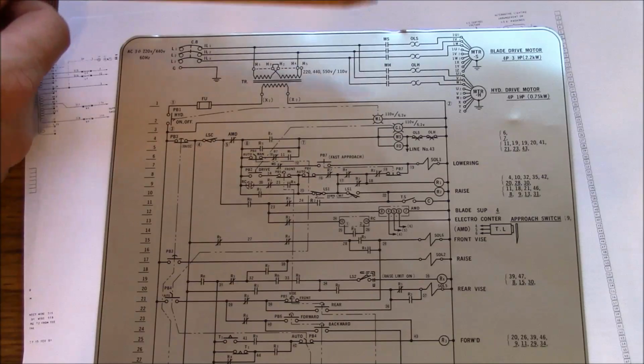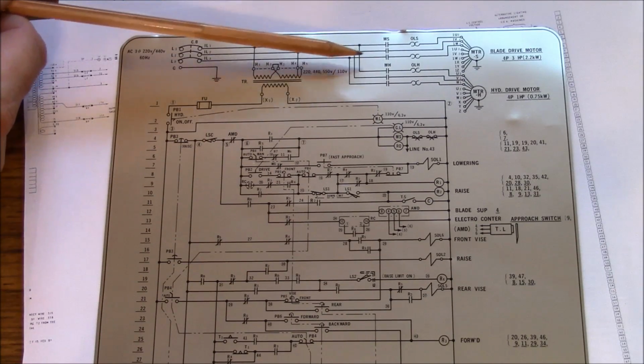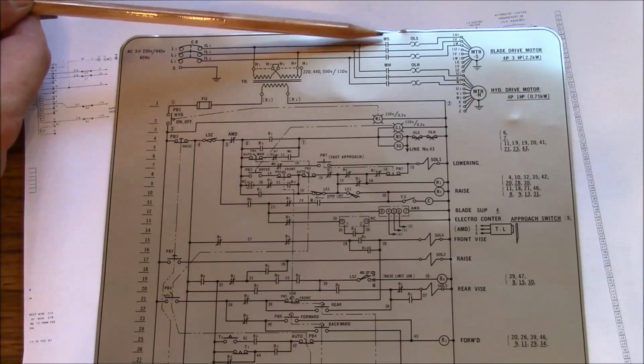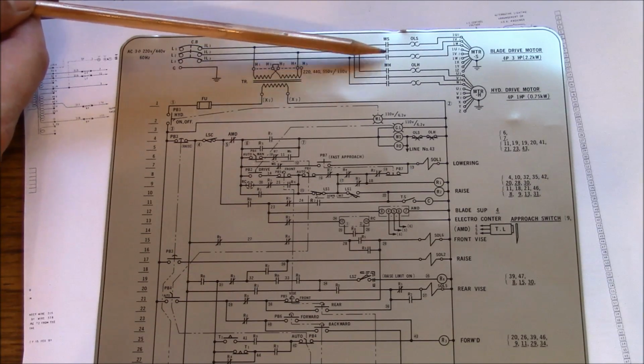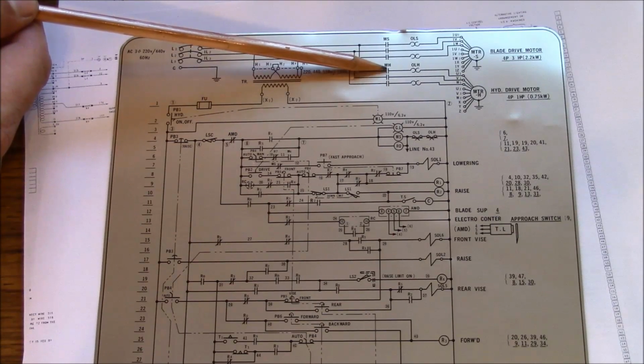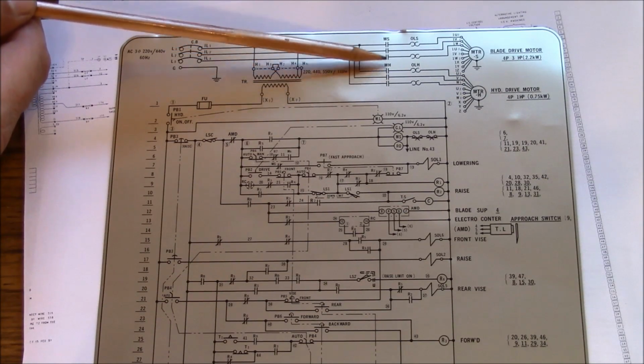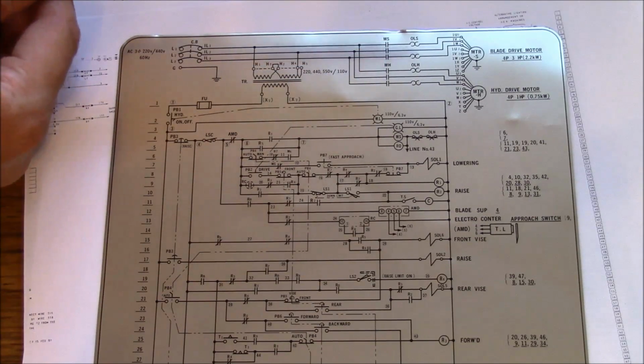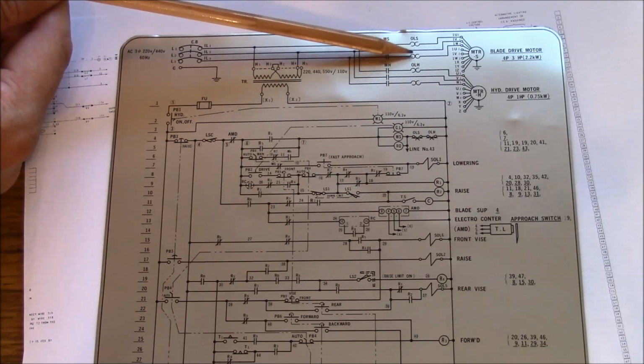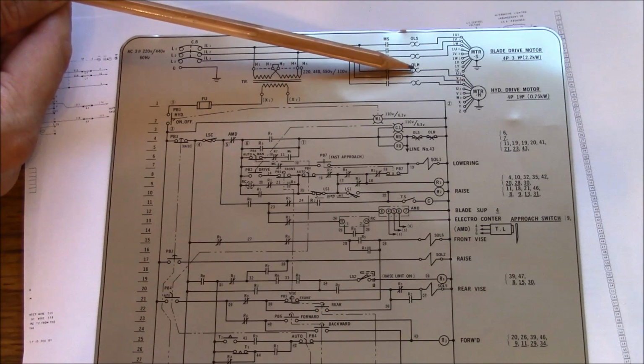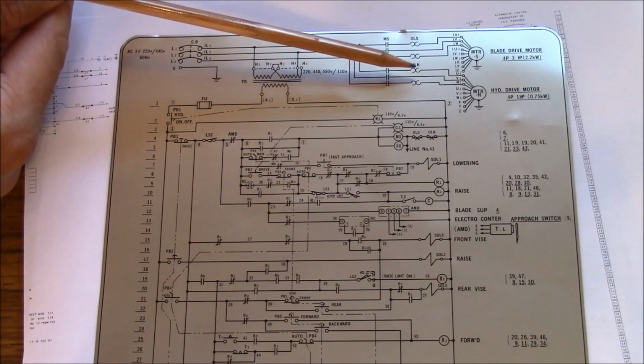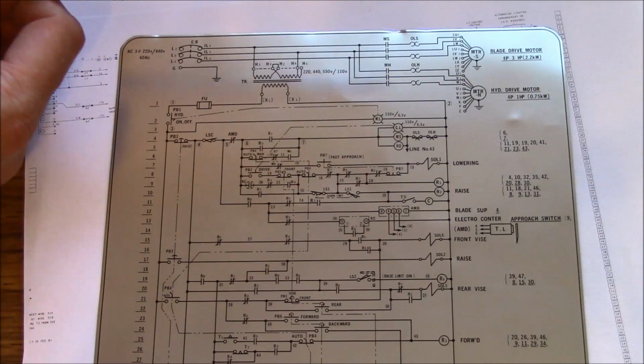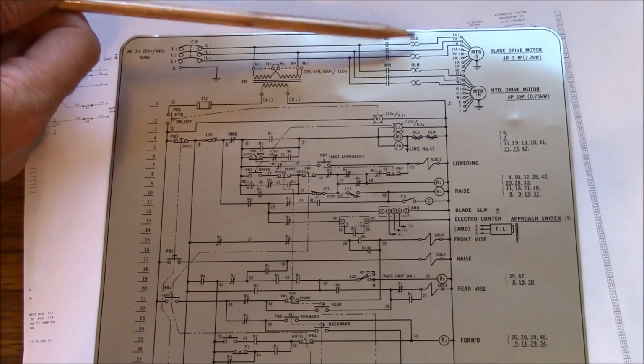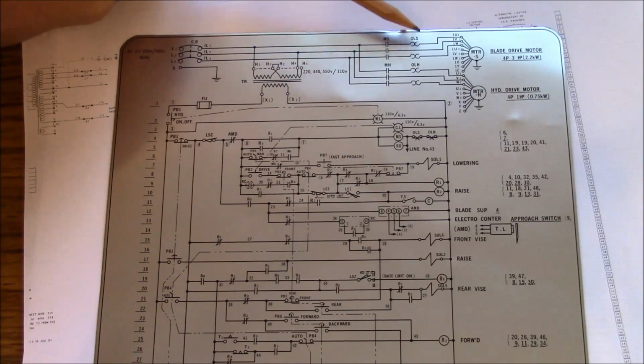You can also see that the three-phase power comes over here and goes through MS and MH, and these are contacts, but large contactors, motor starting contactors basically. Then you see this squiggly line here, OLS and OLH. Those are the over temperature, over current protection for the motors, what some people call heaters, basically the thermal protection for the motor winding. So if the motor gets too hot, under too much of a load, these are going to open up and kill the motor.